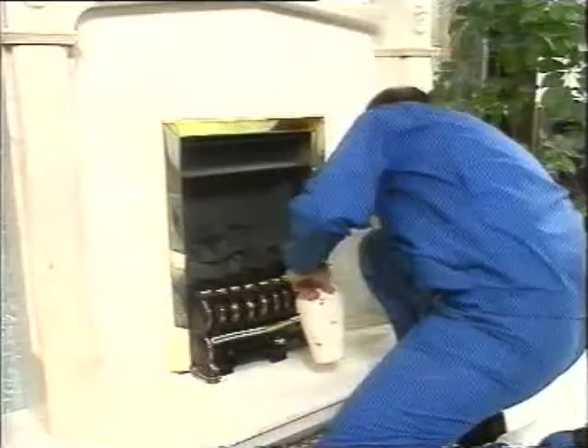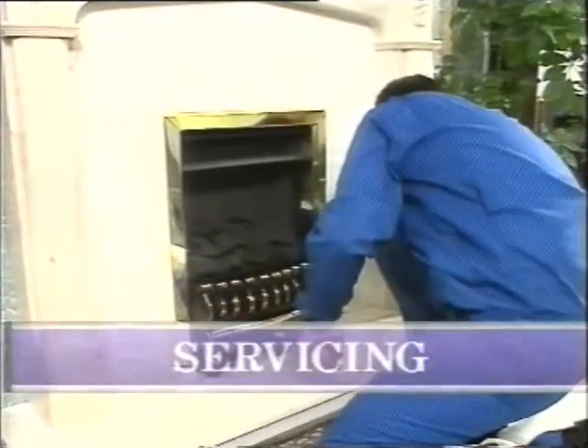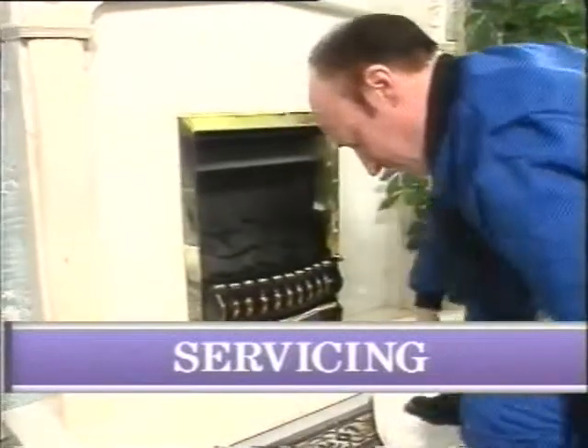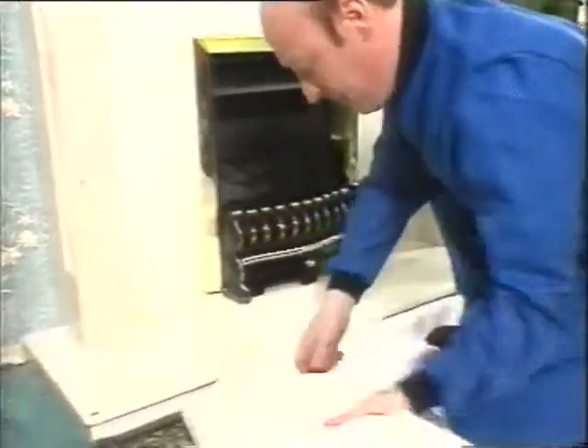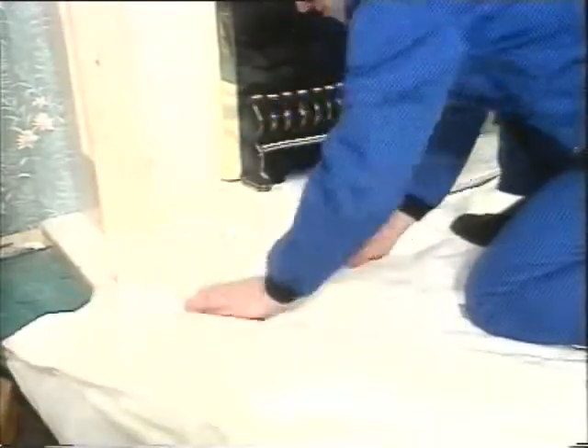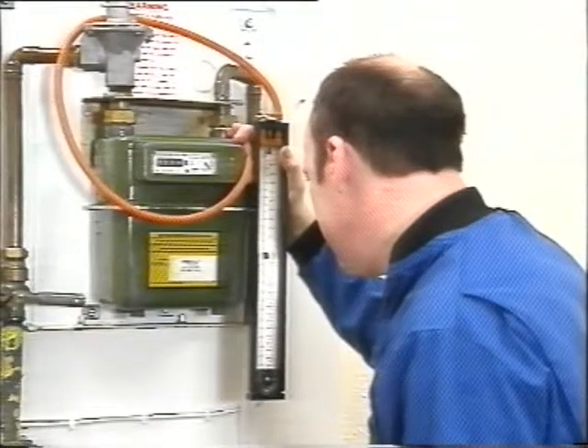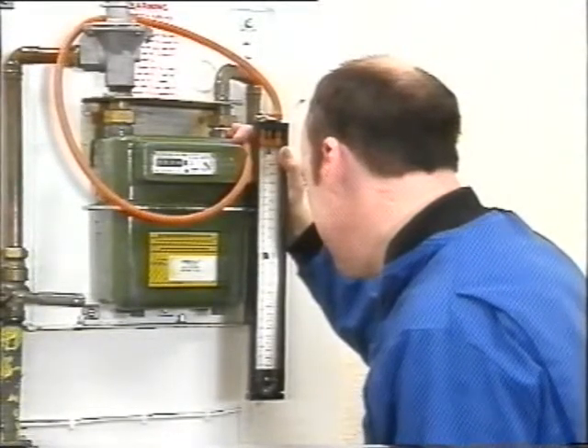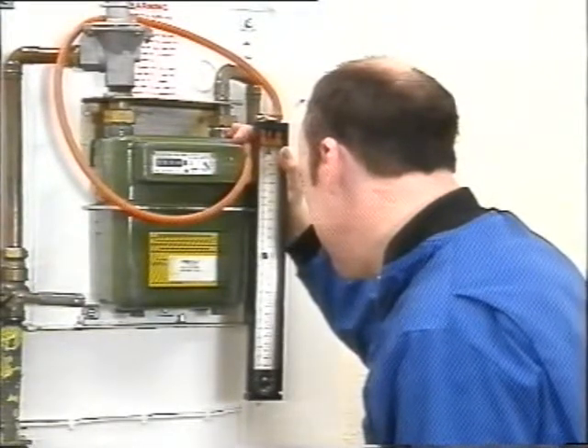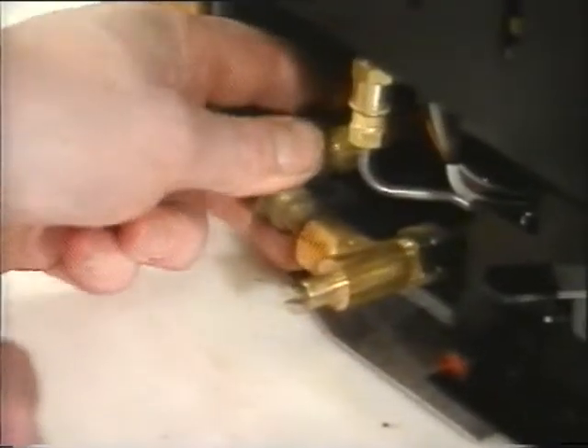Servicing of ILFEs and DFEs is the same systematic procedure we've already described. Start by clearing the work area and laying down dust sheets. Test the gas installation for soundness, isolate the appliance from the gas supply, then disconnect it and remove the fire.